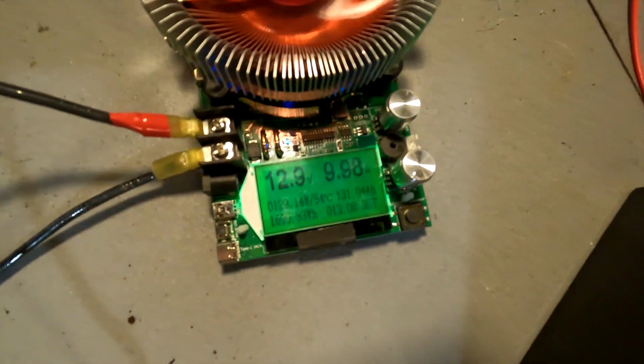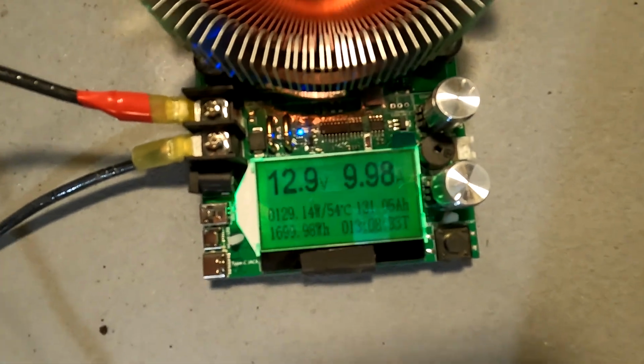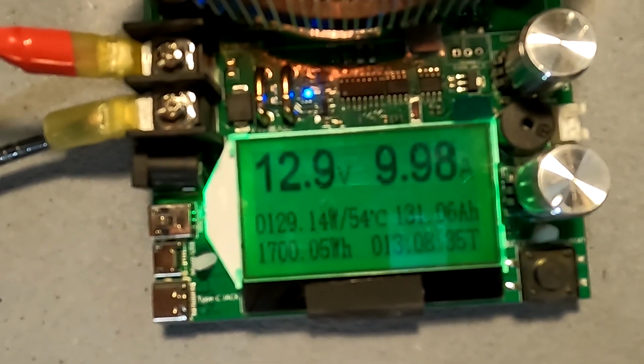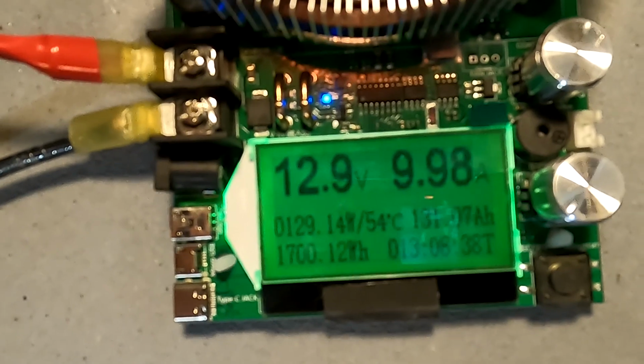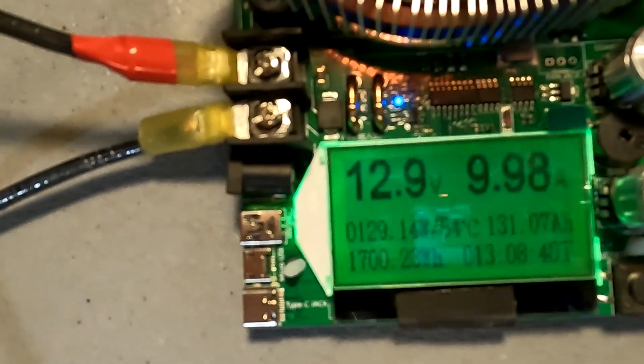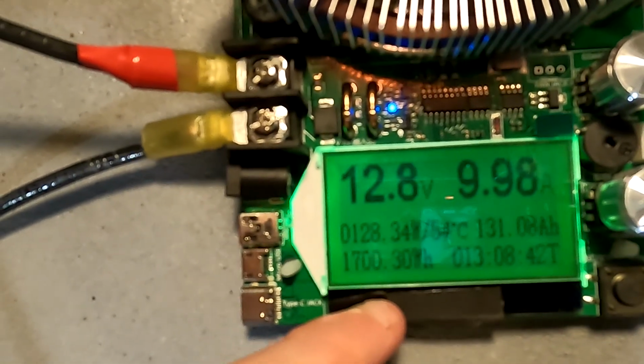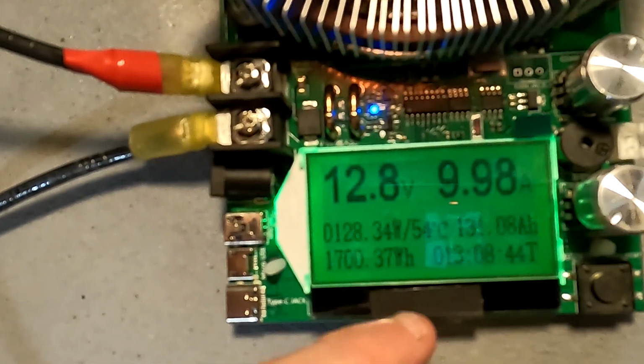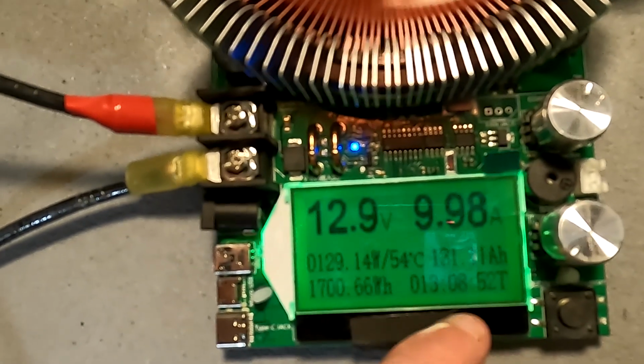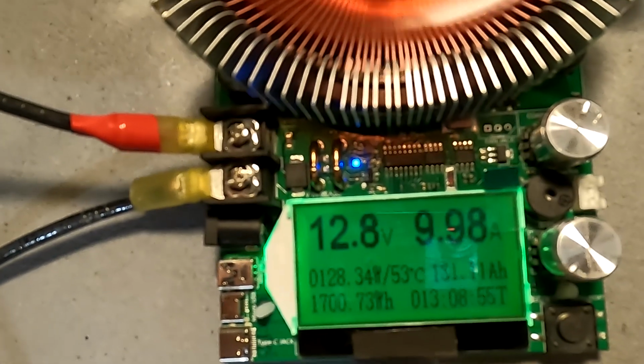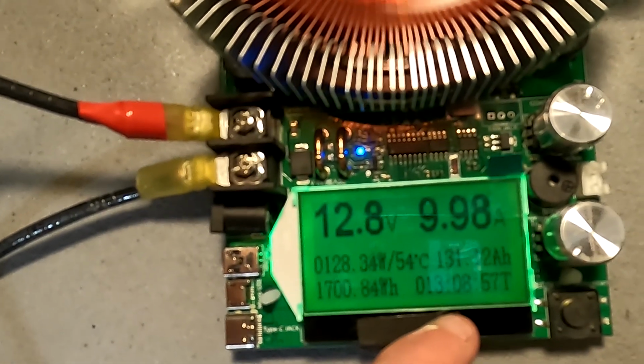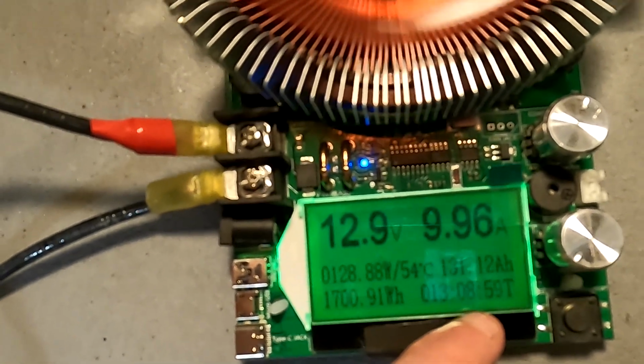Okay, it's now 6:30 in the morning, let's check out the battery tester to see what our numbers are so far. It looks like the tester says our battery bank is at 12.9 volts, still running at almost 10 amps of discharge. Our total watt hour usage has been 1700 watt hours, and our total amp hour depletion is 131 amp hours. The test has been running for 13 hours and 8 minutes.